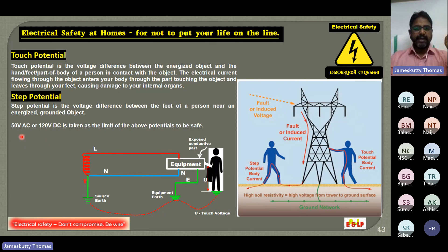This definition is taken from IS 3043:2018, and it is a bit more explanatory. Touch potential happens through touch, while step potential happens through a potential difference created on a surface due to the potential gradient from an energized object. I will explain potential gradient later. In the case of step potential, the two points of contact on the body may not necessarily be the feet themselves.